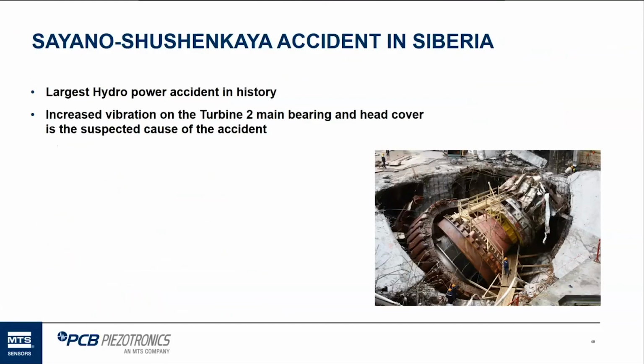I wanted to just talk about the largest hydropower accident in history. This was in Russia several years ago. Basically, a lot of people died in this accident. There were 6 turbines at the Sayano-Shushenskaya plant in Siberia, Russia. They had increased vibration on their turbine unit 2 main bearing and head cover. From what I understand, I'm not sure, they didn't have any vibration monitoring installed, so they didn't really know it was vibrating as badly as it was until guys in the control room started feeling vibration under their feet and called for a plant evacuation. So it was a big disaster.